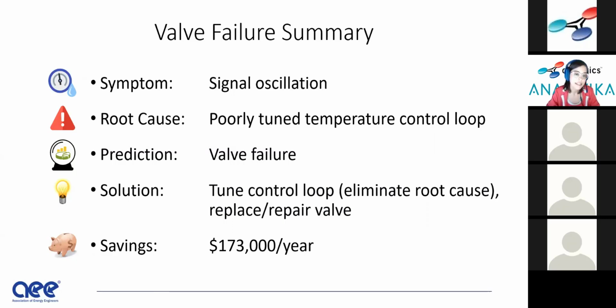What are these numbers? This is an annualized number. I always get this question. If that fault that we just saw had happened for an entire year without being repaired, that's what that number represents. We have methodology and assumptions and all of these things, but generally, the more airflow that the unit is providing, more CFM, the more hours it's running, so 24/7 operation, the more savings you're going to have, right? And your delta T, your delta temperature, your delta airflow, and how many hours you've got. And that's, for this case, your savings.